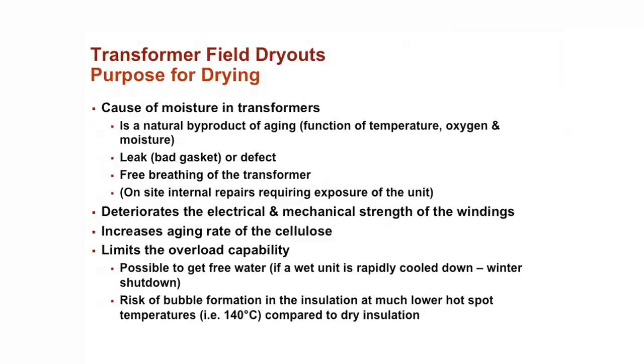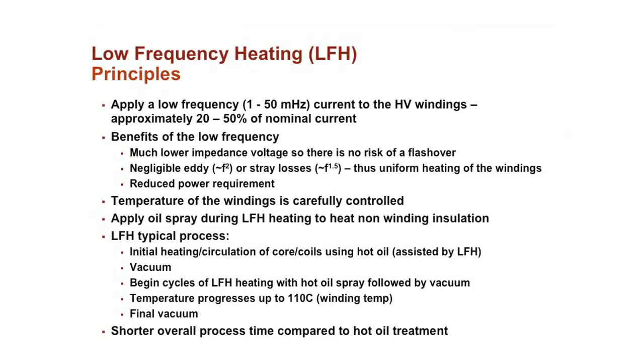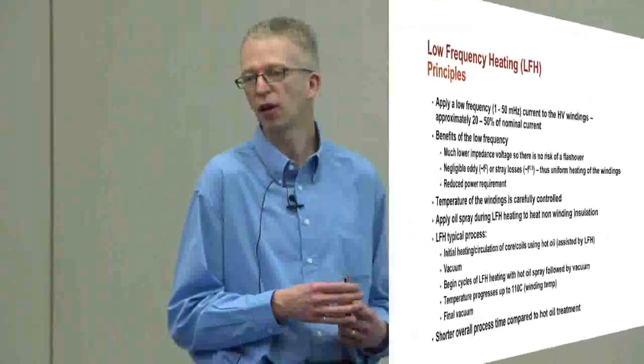There are different ways of drying out a transformer. The traditional way is to drain it and use a hot oil vacuum system. There's another way, which we think is better, using low frequency heating. You put a low frequency current on the windings, and by doing it at a low frequency, you don't have any leakage flux in the windings. Because of that, you don't have a hot spot in the winding. So basically, you can have the same temperature across the whole winding as you're doing this heating. And you can do this at pretty high temperatures, up to about 110, 115 degrees, and you can really effectively dry out a transformer in the field.